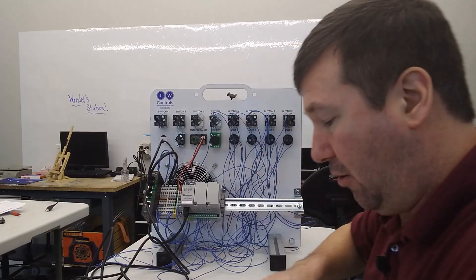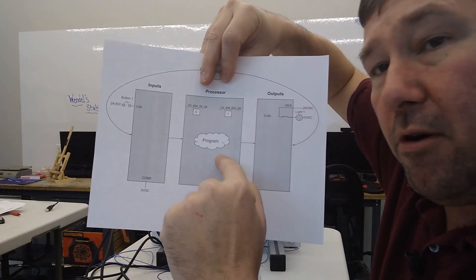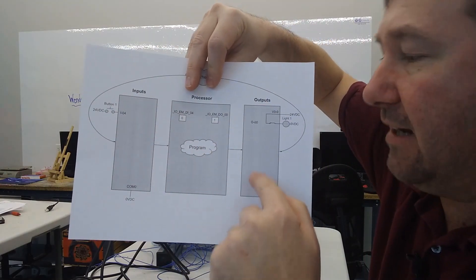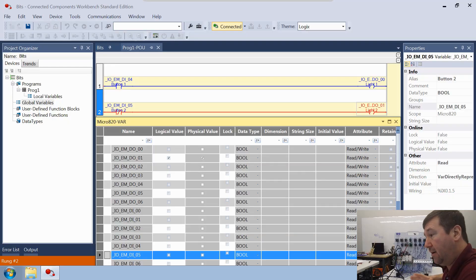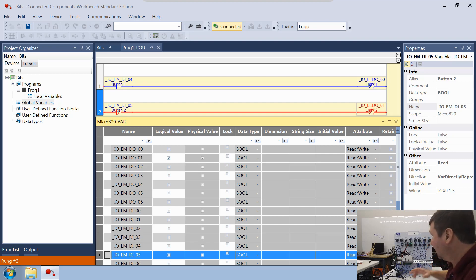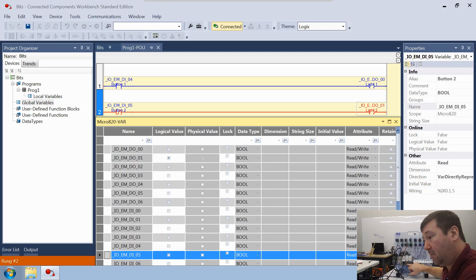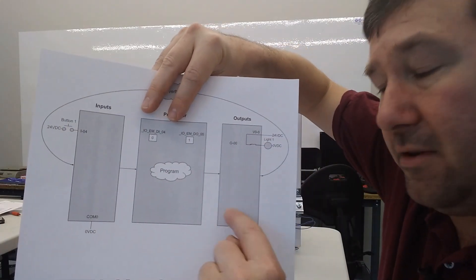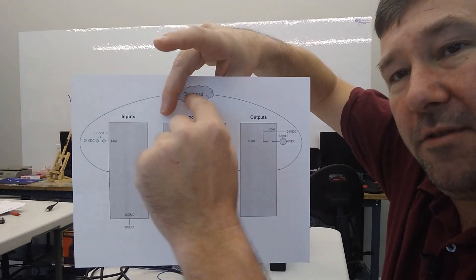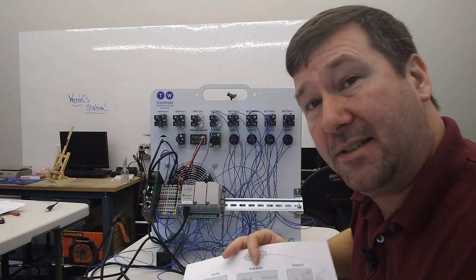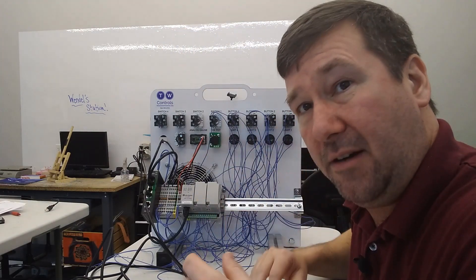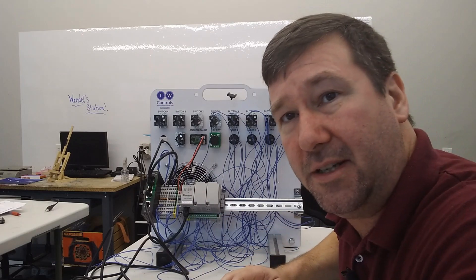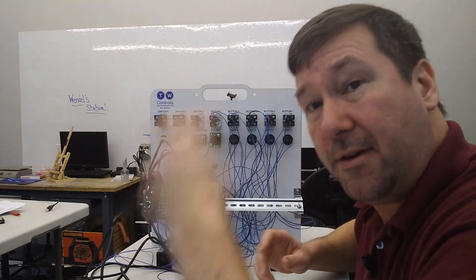Now we're at the end of our program. Once we get to the end, it's going to update its outputs. It looks at Output 0 — I have a 0, turn off Output 0. Output 1 has a 1, turn on Output 1. Output 2 has a 0, off. Output 3 has a 0, off. It goes through that very methodical sequence with every one of them, does a little overhead, and does it all again. All that happens in like a millisecond — it just keeps repeating that process over and over.